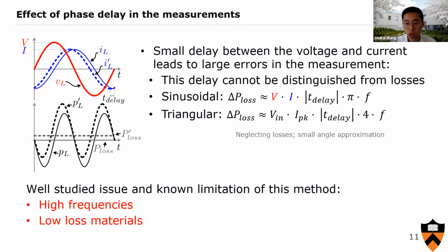One problem our voltage and current measurement poses is something called the phase delay error. This happens when you have an oscilloscope collecting the voltage waveform from one probe and the current waveform from another. There's always some small delay between these voltage and current measurements, due to different probe lengths, scope sampling itself, or other probe-related issues. This delay can give rise to a large average power difference.